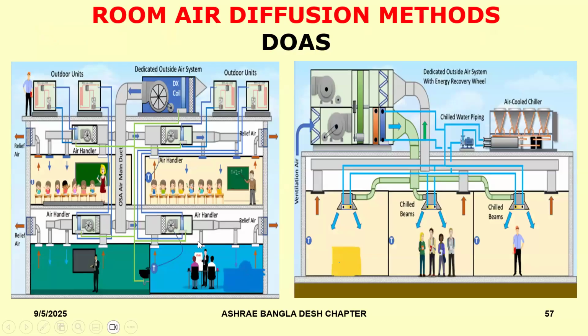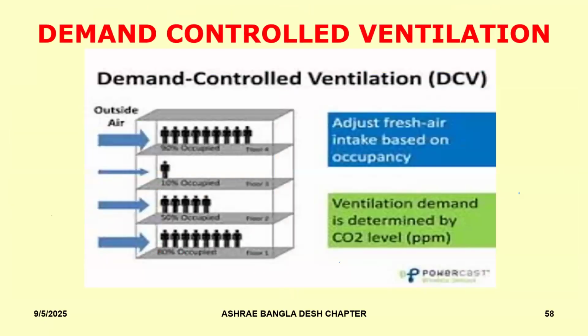For example, in this space, we got, let's say, 2 classrooms here. And in these 2 classrooms, one has got less number of students, the other one may have more number of students. So obviously, the one that has got less number of students will require less amount of outdoor air as compared to the one which has got more students. So what do we do in that case is we use something called demand control ventilation. So what happens then is that the dedicated outdoor air unit will supply as much air that is required for each floor or each space, depending upon what is the demand.